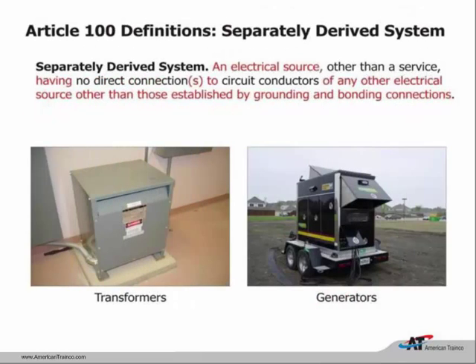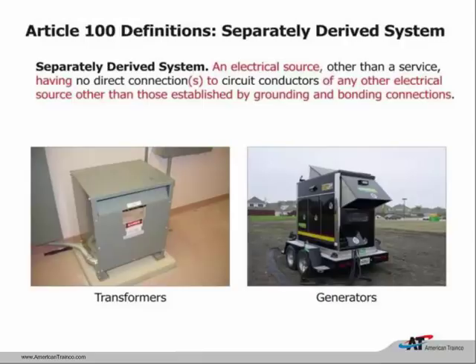Another definition they've refined is separately derived system. The most common example on the left is the transformer—no direct electrical connection from one source to another; it's all inductive. On the right is the generator, and when we get to Article 445, manufacturers of generators will have to indicate whether their generator is a separately derived system, meaning the neutral is bonded to the generator and its frame. We also have to be careful looking at transfer switches—a separately derived system would require a four-pole transfer switch to transfer the neutral along with the ungrounded conductors.